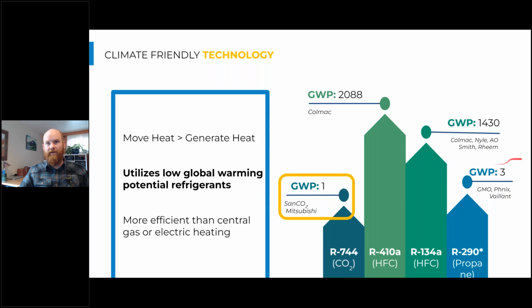We also have some US manufacturers that have been providing heat pumps that use R410A or R134A. Colmac is up here in the Northwest. Nyle is on the other side of the US in the Northeast. And then we have A.O. Smith and Rheem, a few of the bigger players in the water heating world. All of these companies have heat pump water heaters that are really efficient, often operating at a coefficient of about 3.0, or 300% efficient, and great options for water heating. However, one huge advantage of CO2 is it can work at rather cool ambient air temperatures, so in our cold climates, and it also has this low GWP. So I think I've started to see a lot of this market moving towards these CO2-based systems, or an alternative, which is held up by a bunch of red tape right now, is R290, and that's propane.